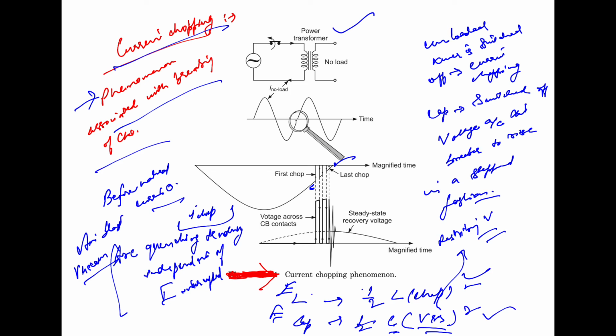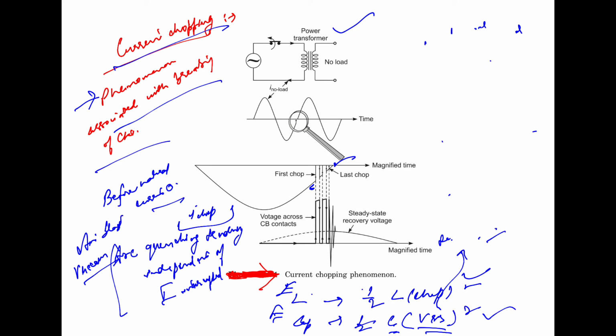The restriking voltage caused because of the current chopping is given by this expression. By equating both these expressions, the restriking voltage that is obtained is given by equating these two, and we finally get V restriking is equal to I chop times the square root of L by C. So from the above expression, what do we get?